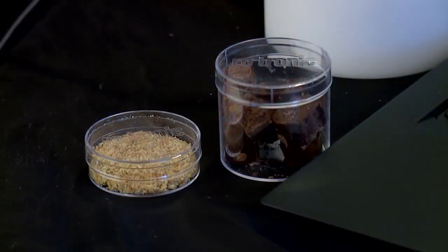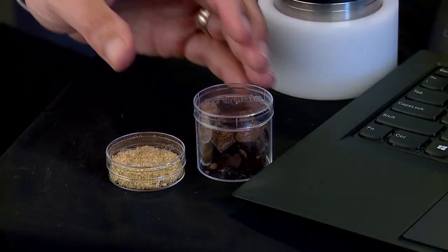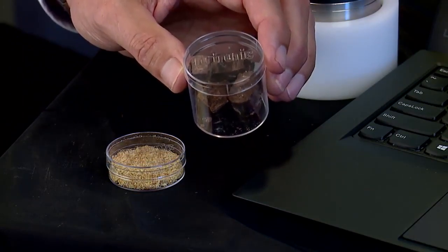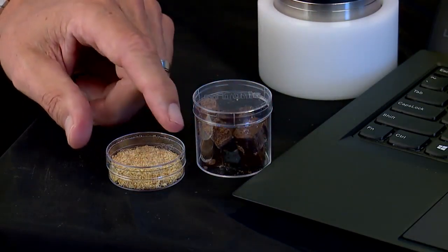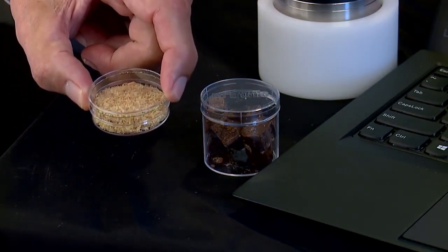Rotronic water activity instruments all have the choice of large and small sample cups. The large sample cups are perfect for measuring solid samples of product without the need for grinding, while the small sample cups are well suited for the measurement of liquids and powders. In both cups, the test material should be filled to the line on the cup, but be careful not to overfill the sample cup. In all cases, the sample material should be at a stable temperature.